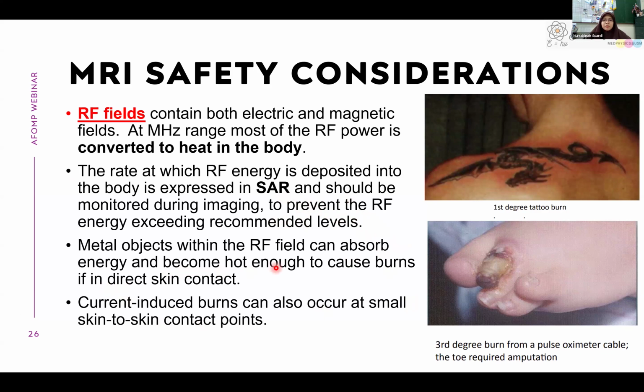And metal objects within the radio frequency field can also absorb energy and become hot enough to cause burns if in direct skin contact. Current-induced burns can also occur at small skin-to-skin contact points. In the image over here, I show that those having tattoos who underwent the MRI may get a first-degree tattoo burn, because the contents of the tattoo also include some metallic materials. And the image over here is a third-degree burn from a pulse oximeter cable. The toe at the end required amputation.